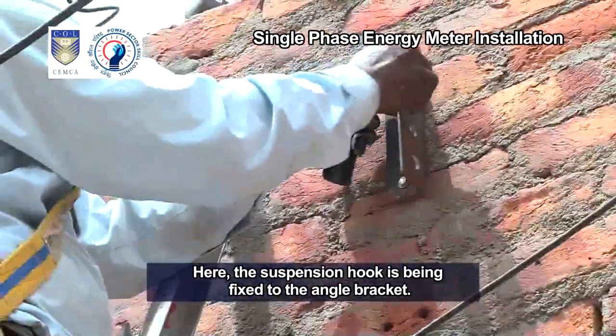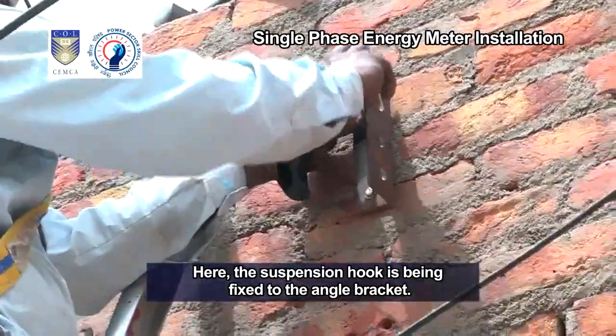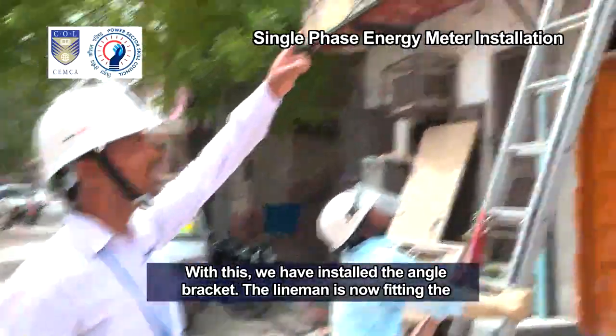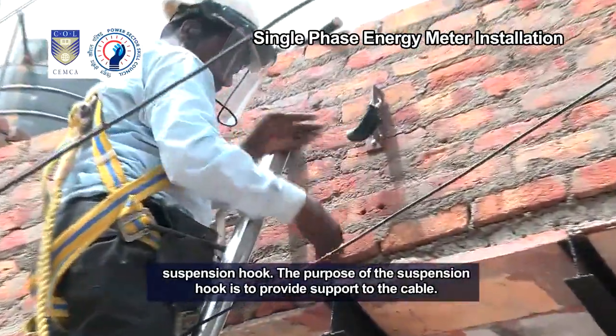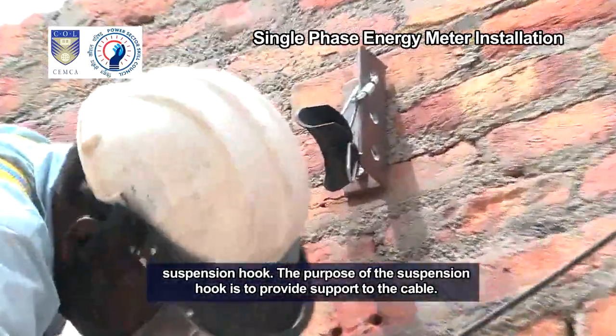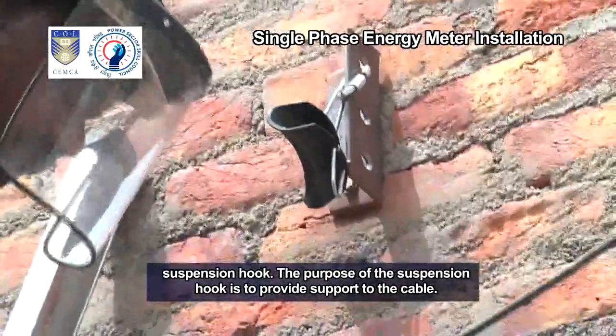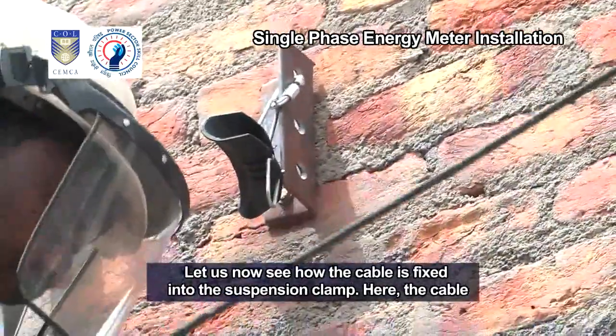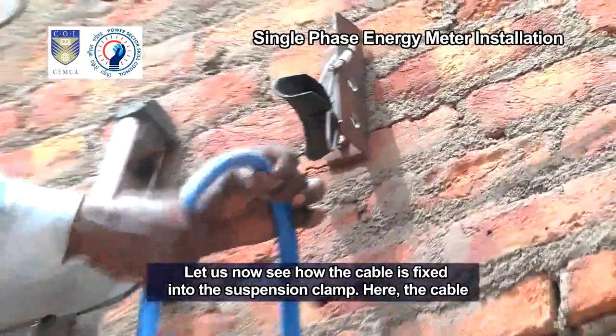Here, the suspension hook is being fixed to the angle bracket. With this, we have installed the angle bracket. The lineman is now fitting the suspension hook. The purpose of the suspension hook is to provide support to the cable. Let us now see how the cable is fixed into the suspension clamp.